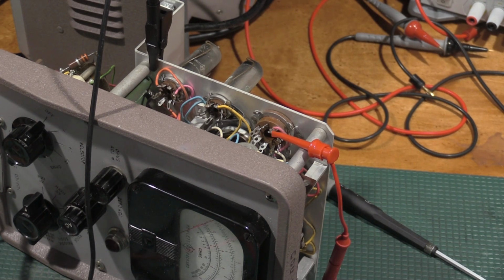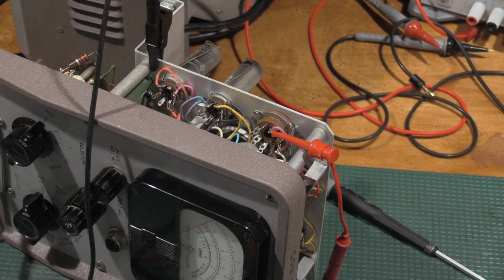But my general consensus right now is this tube is toast, so I want to be real careful not to lose this spring contact. I'm going to need that for the replacement tube. And as you can see, when I insert the tube, the meter kind of goes nuts, which is to be expected. But so we don't lose any of the contacts, all that's put back together. And the reason the capacitor saw 300 volts across it when I measured it on the meter was because it is both on the positive, but it's referenced to the negative supply, so it's actually doing double duty. So when that tube gets here, we will continue and see if that's our problem or if we have other issues. These meters are pretty simple to work on, so I'm hoping that's our fault, but I will know here in a couple of days.